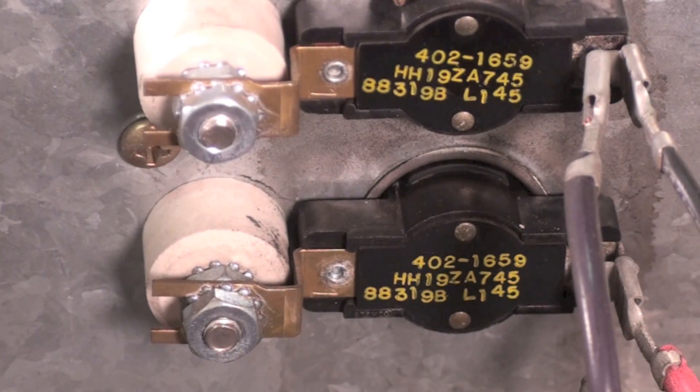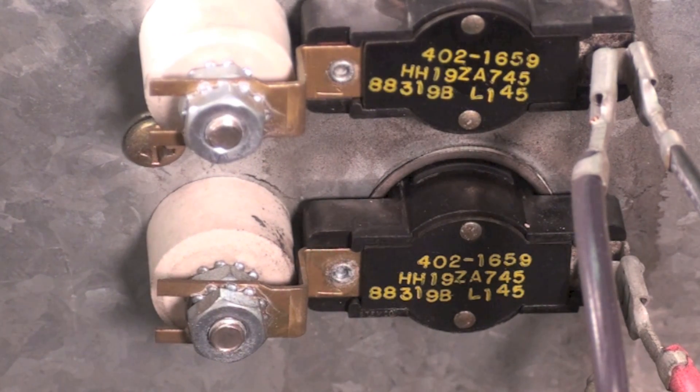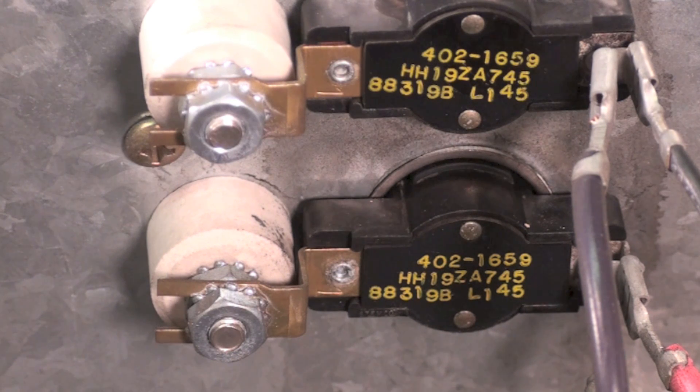Let's say somebody does not change your filter - some other reason there's low airflow - these will start shutting off. But you know, these are automatic reset, so they're just going to reset, start again, overheat, shut off, overheat, shut off.